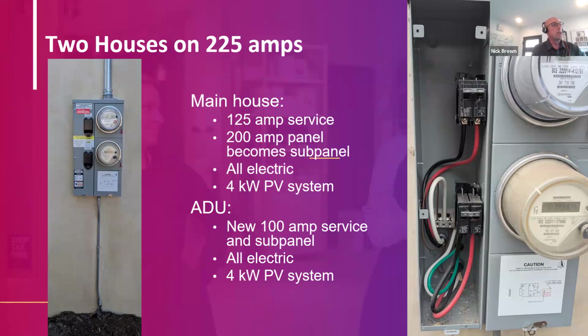225 amps total. The main house, on the right picture, has a 100 amp breaker for the ADU meter and a 125 for the main house. That shows the main house, even though it's 2000 square feet and all electric, can get by fine on 125 amps. Many of your single family homes may fall under that as well, and that's with an EV charger and solar.